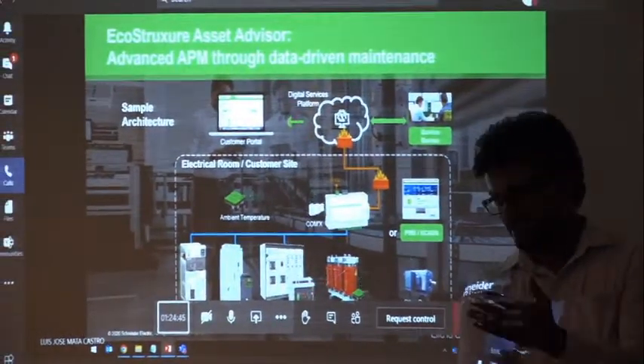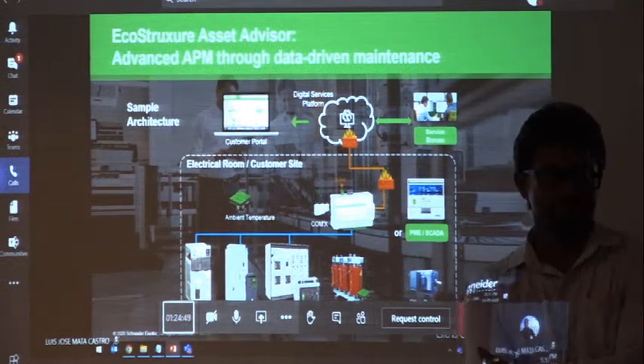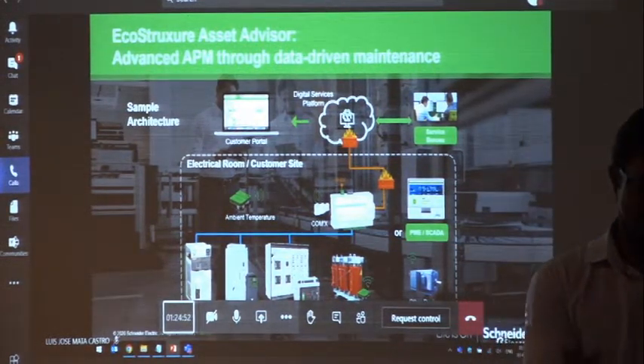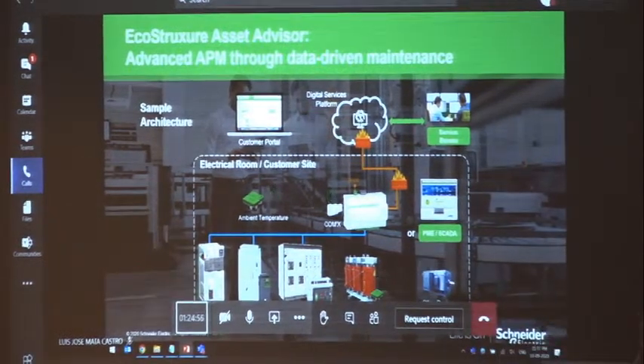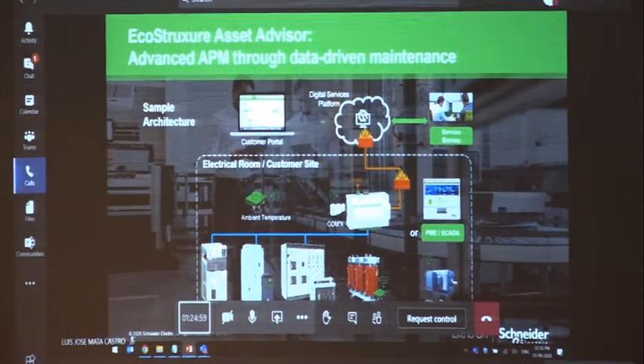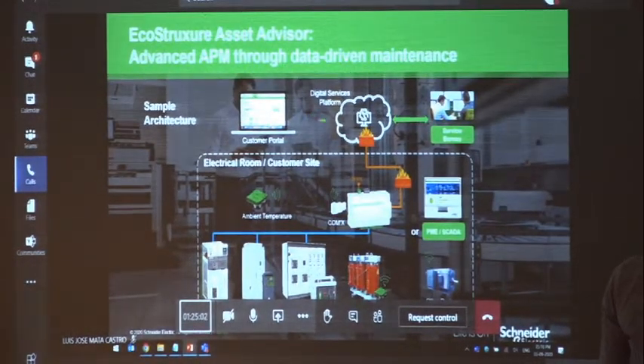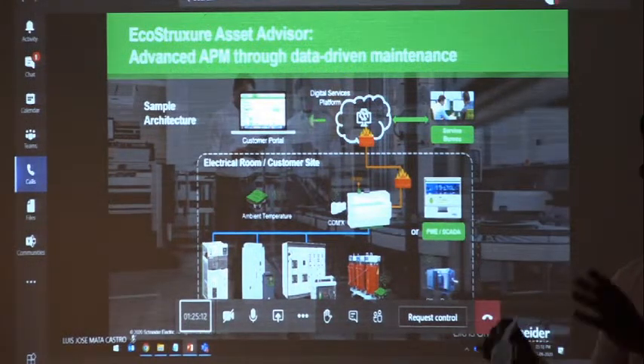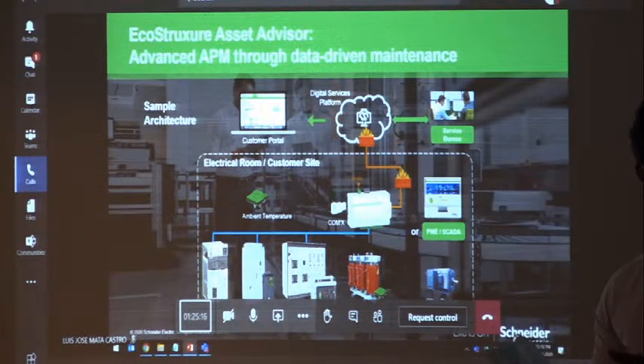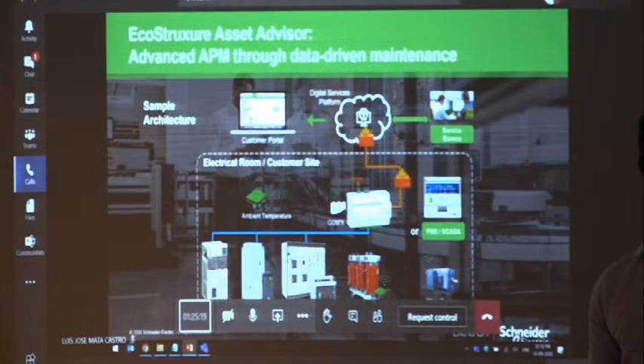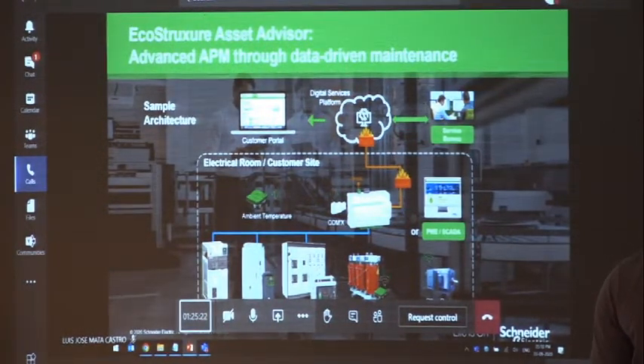This is already being practiced. The technology is not a new thing. Having a BMS in a building is conventional, but this goes beyond that. If you have a BMS, we can take all the data into the system, but what will you do with this data, and what will be the next action? That's the advantage, because we have the asset advisor, asset management software. From the BMS it extracts the data it needs and predicts your maintenance, how it should be and what needs to be done, rather than going for reactive or just preventive maintenance. This is the next platform, because all the big buildings, even in Sri Lanka, have BMSs, but we don't take the maximum out of that data.